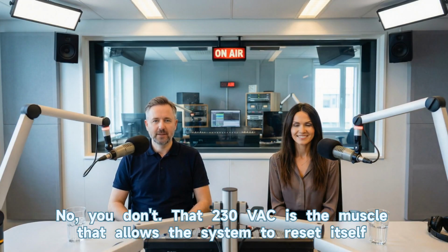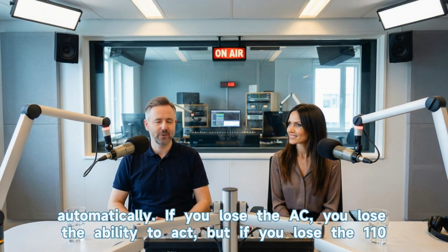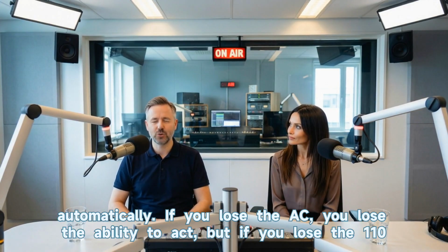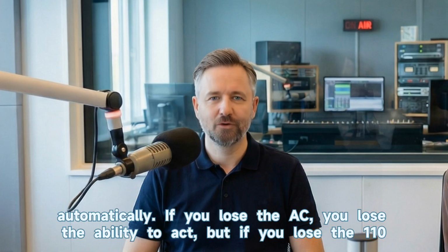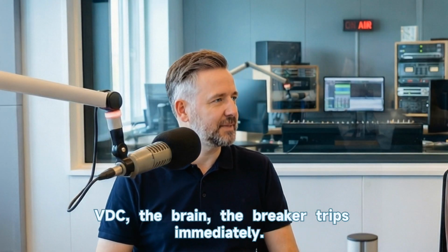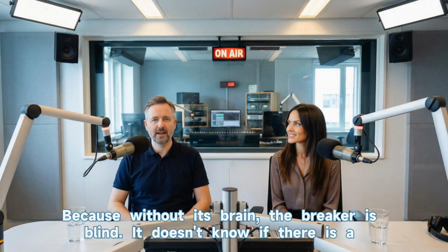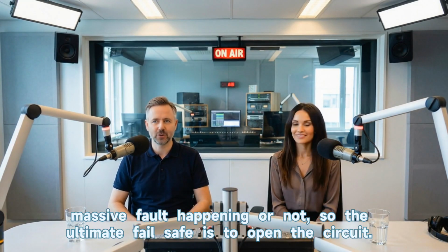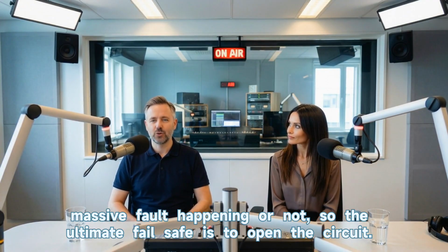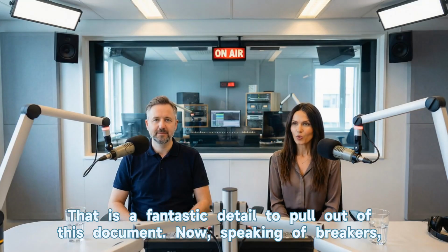No, you don't. That 230V AC is the muscle that allows the system to reset itself automatically. If you lose the AC, you lose the ability to act. But if you lose the 110V DC, the brain, the breaker trips immediately. Why does it trip if it loses DC? Because without its brain, the breaker is blind. It doesn't know if there is a massive fault happening or not, so the ultimate failsafe is to open the circuit. Safety first. That is a fantastic detail to pull out of this document.